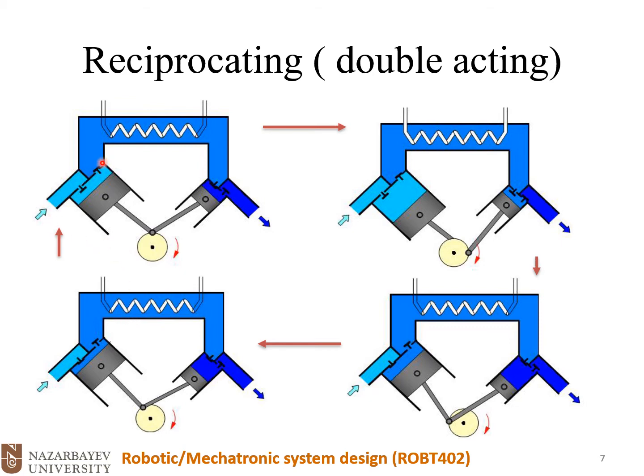At the first stage, why are we calling this double acting? Because we have 2 cylinders and 2 pistons here, as you could see. We have a crank here, and it goes through the first stage and the second stage. You see that the volume of the first one is larger than the volume of the second one.